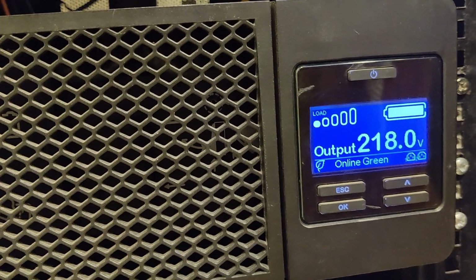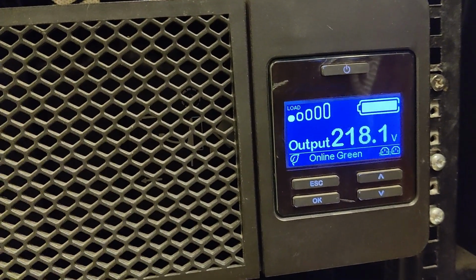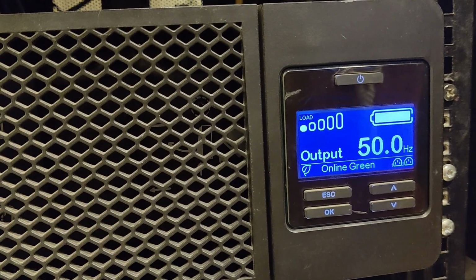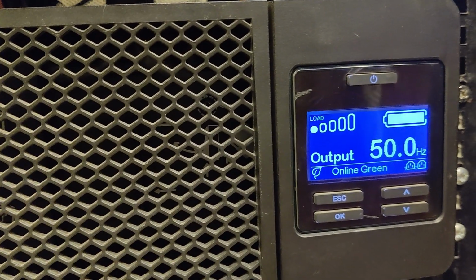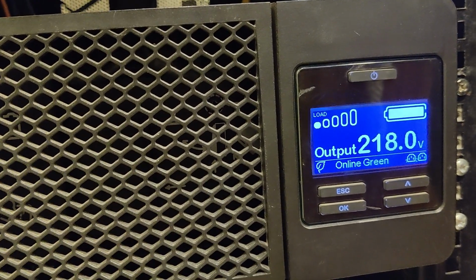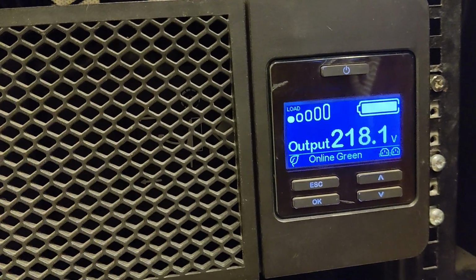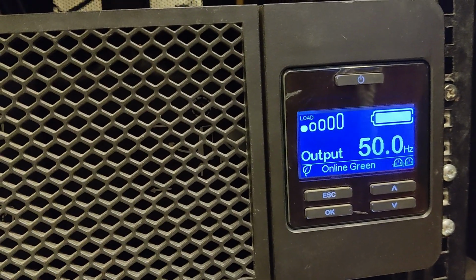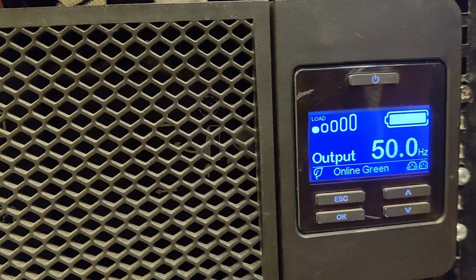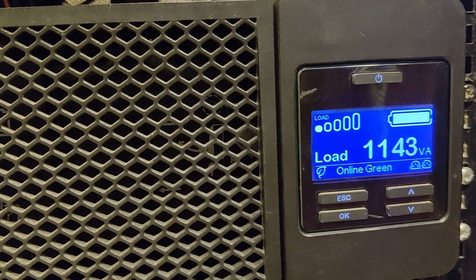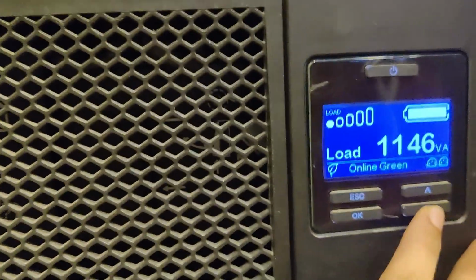Hello everyone. Today we've encountered an issue with our APC UPS unit, SRT5000 VA model. I'm trying to access the APC UPS webpage, but it seems like something's gone wrong, so we will diagnose and solve the problem. First of all, we will check our UPS network setting and confirm everything is okay.